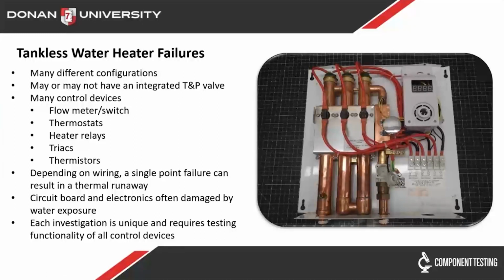They have many control devices on them. This one I'm showing is electric, but there's also gas. There's some combination electric gas. There's tons of configurations out there. One constant is that they all have the flow switch. Most of them have thermostats, which are thermal protection. They're kind of like a safety redundancy. There's heater relays, which tell the heaters when to come on. There's some triacs on some of them. Triacs are like electrical relays. And then there's thermistors, which simply monitor temperatures. And these all feed into a control board, which kind of has a micro on it, which interprets all the inputs and controls some outputs.